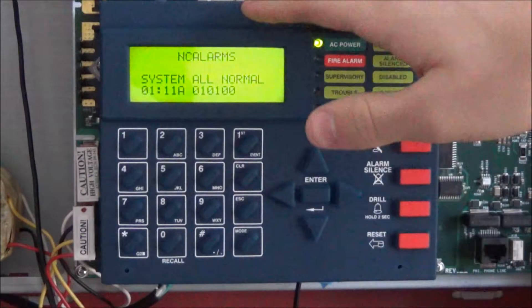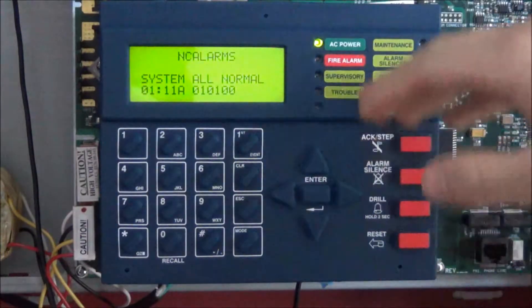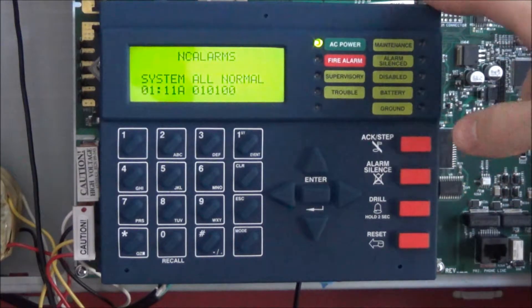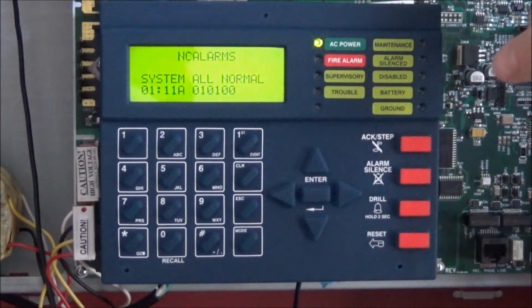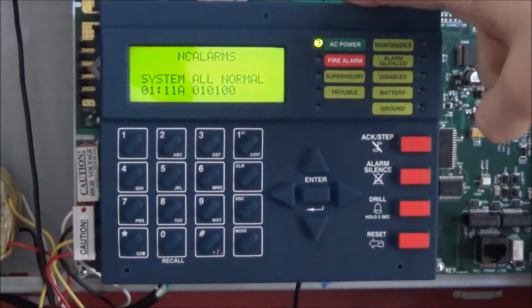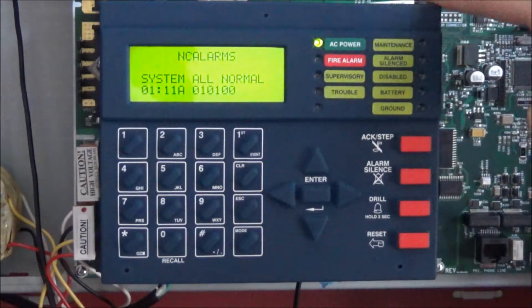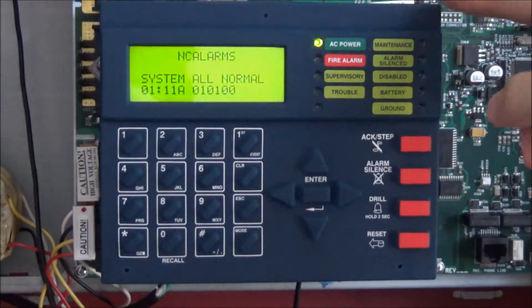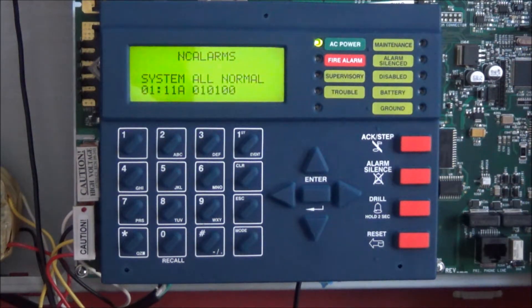Let's have a look at this panel. Obviously this is the interface board. This panel is incredibly flexible — love it already. It has 4 NACs, 3 programmable relays, and 1 SLC which supports 99 modules — which includes pull stations — and 99 detectors. So it's pretty expansive; best for moderate sized applications, or in the modern day smaller size depending on where you live.